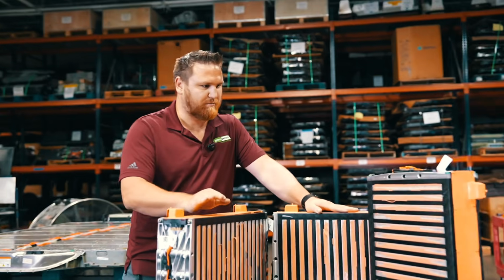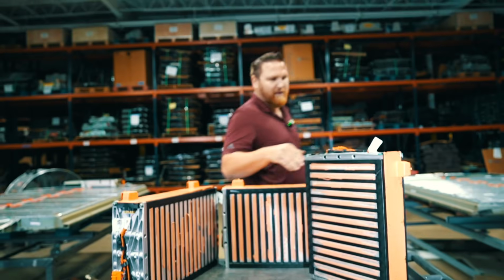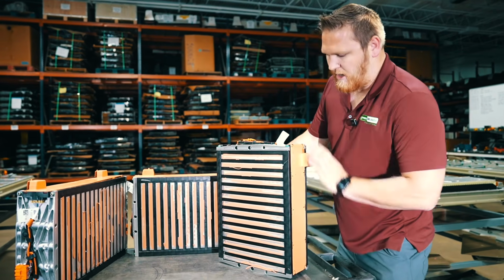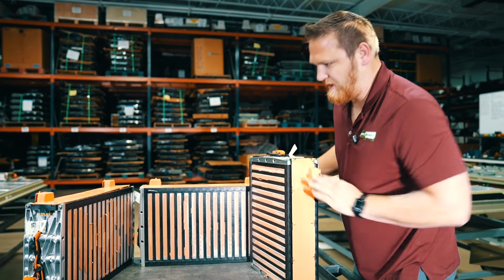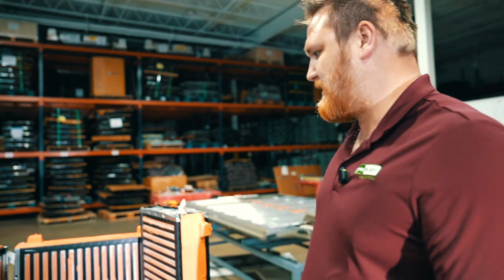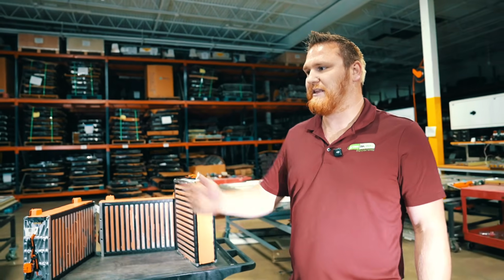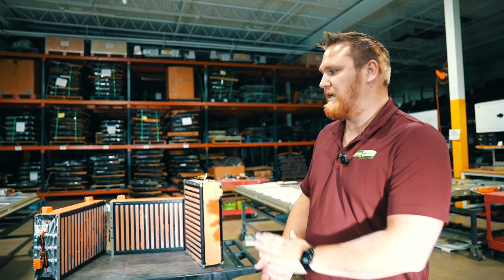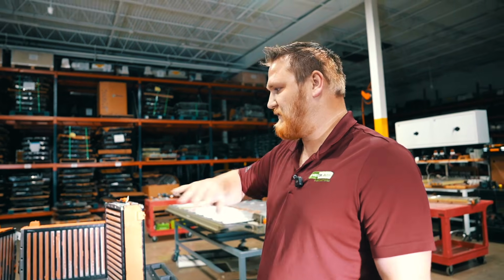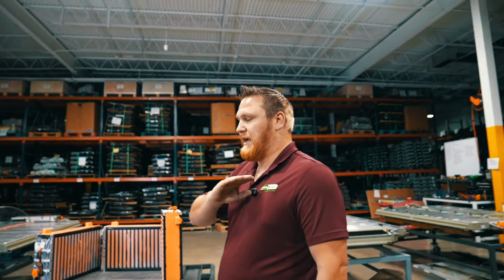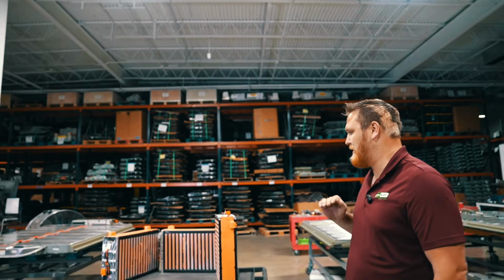So here we have the 3 modules, and we have to stack them this way because on the bottom we have a thermal interface, and if we laid that down on anything, that's gonna create a mess. Obviously getting the modules out wasn't easy either, those things are definitely stuck down pretty well. We're gonna have to clean these modules completely, clean those cooling plates you saw earlier also completely, and apply new interface to get them back to spec.